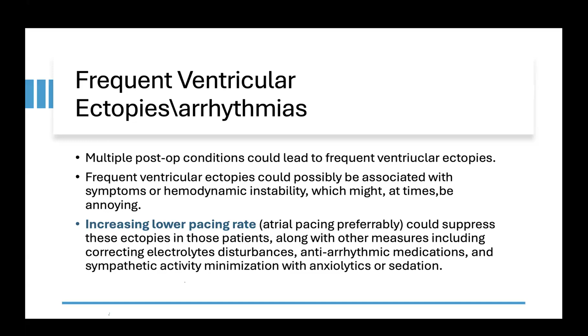In patients with recurrent therapies or electrical storm, other than increasing the lower pacing rate, they could benefit from prolonging the detection time to allow for a spontaneous resolution of the arrhythmia if possible. The other way is we can turn off the shocks and leave the ATPs, and keep the external therapies in use if there were concerns or a need to preserve the battery and the lead integrity.